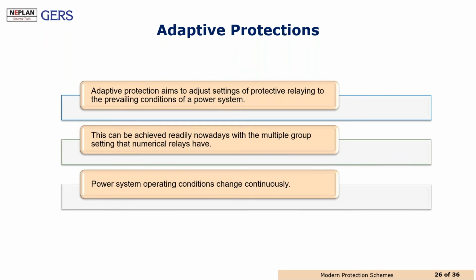Well, another application that we find in modern protection schemes is adaptive protection. Adaptive protection comes from the opportunity that we have to change the setting group in the protection relays, depending on the topology, depending on the loading or generation levels. And we can see how different applications in the state of the art of protection can provide the new settings that the protection should have depending on the topology of the system.